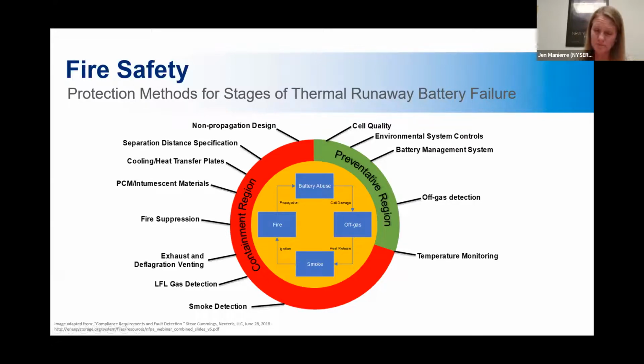Moving along, environmental system controls like air conditioning, for example, within the systems to make sure that they're not overheating. And again, that battery management system, just working our way around. That's what I was describing earlier, the eyes, the ears, the brains of the system, monitoring all of these things and directing it what to do. If it's starting to get a little warm, you turn up the AC. If an individual cell is starting to malfunction and overheat, it can shut that cell down and isolate it from the rest of the system, and so on and so forth.